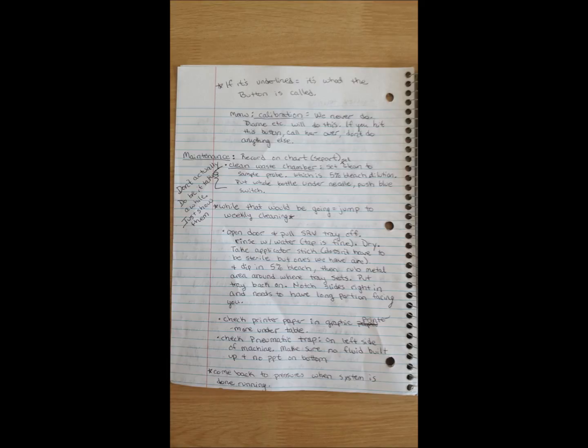That was nice. We're going to check the pneumatic trap. Now, what is a pneumatic trap? This is a pneumatic trap. And if you forget, go to page 2, it's got a picture. All you're going to look for is to make sure we don't have fluid built up in the bottom of that. This is where it moves things through it using pressure. And if it gets too moist, this will have some condensation in there. If it starts to build up too much, it won't be able to push things through. So as long as it's okay, you just check it.